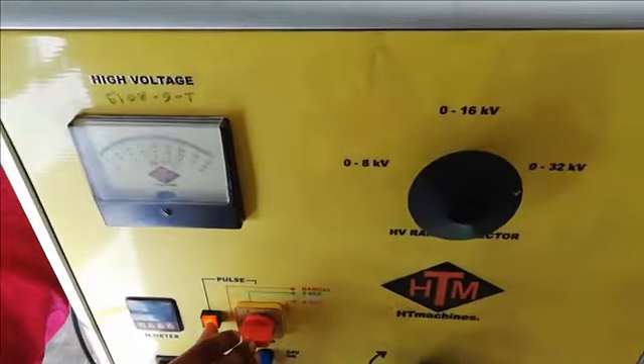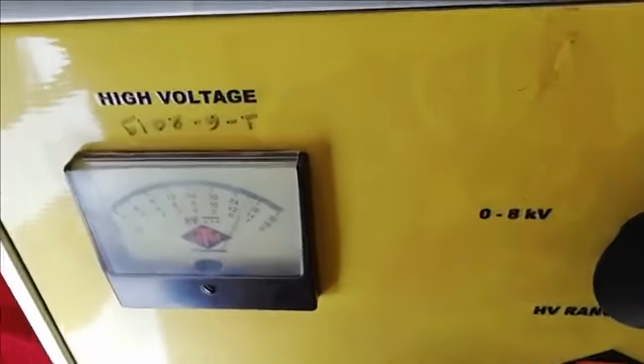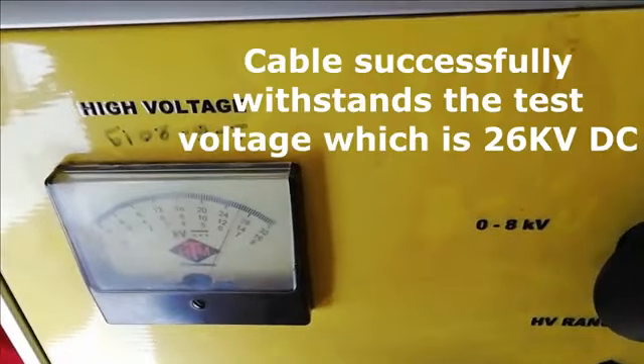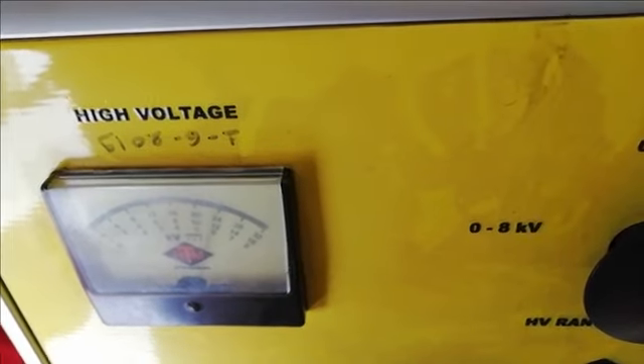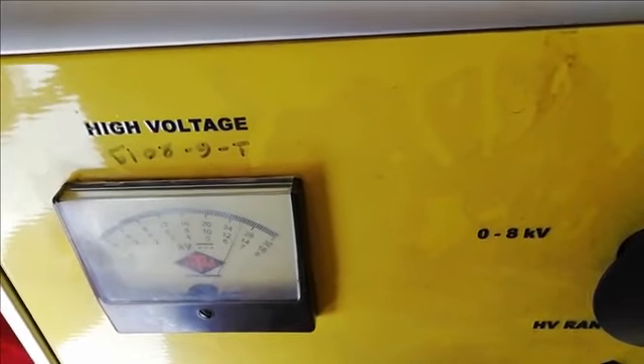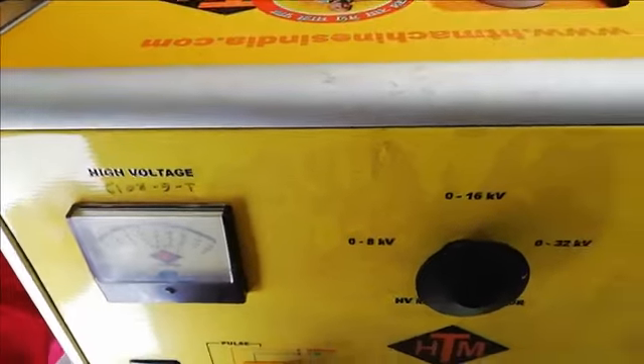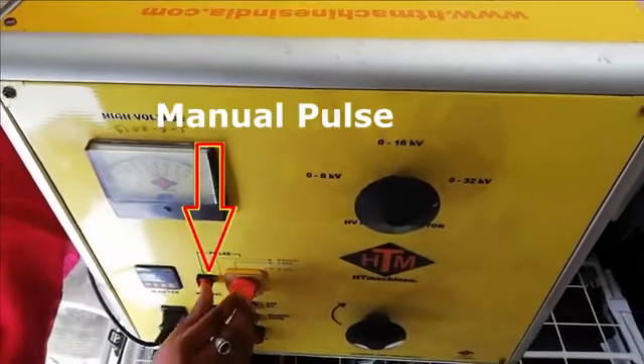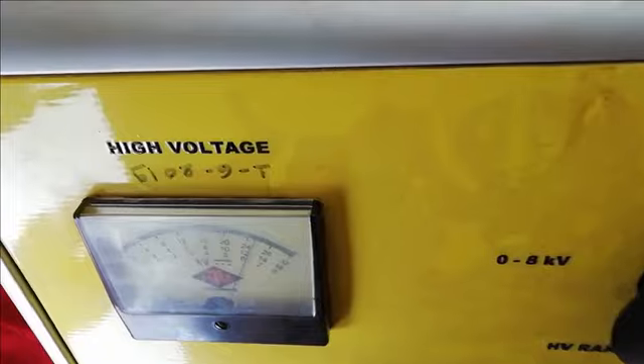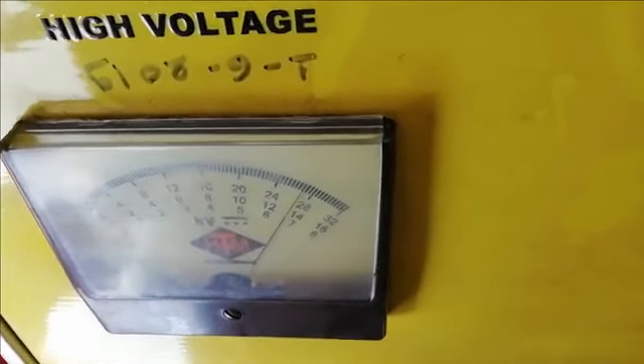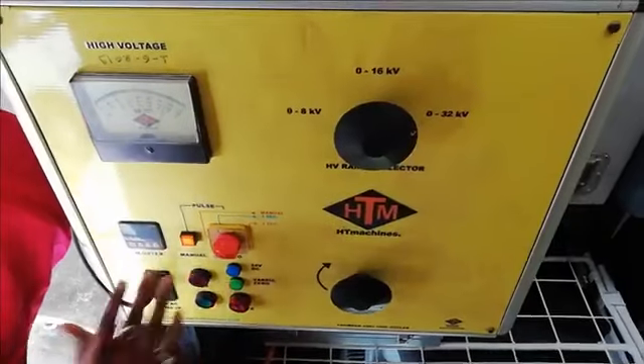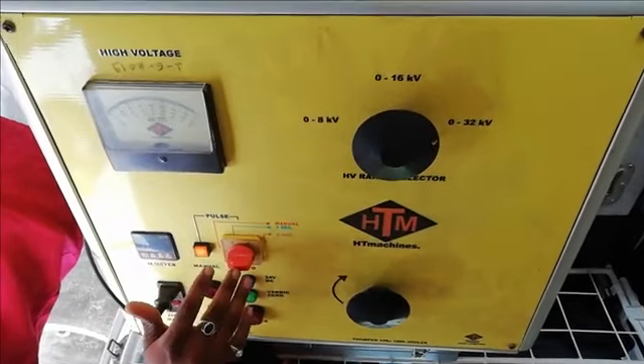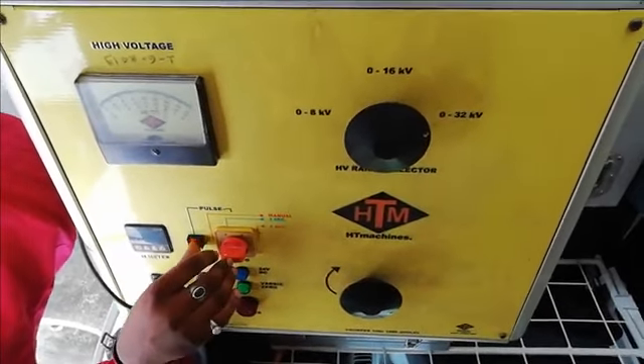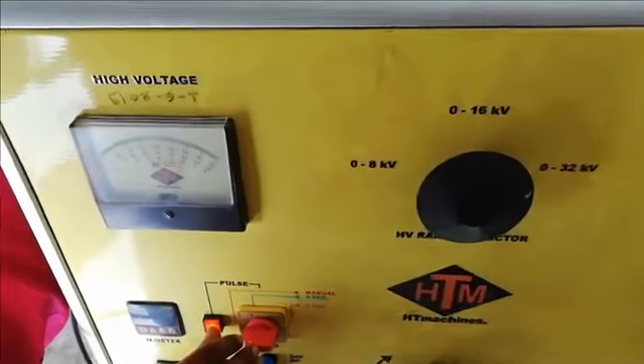In this voltmeter, we can check the test voltage being applied to the cable. We can see that the cable successfully withstands the test voltage, which is 26 kV DC. As per the standards, the cable must withstand this voltage for 1 minute to successfully pass the high pot test. Also in this kit, there is a provision for giving high voltage pulses manually or automatically. For now, the high voltage pulse is given manually. Here, the pulses are given just for demo purposes, whereas these pulses are used to detect the fault location, which we can see in a separate video.